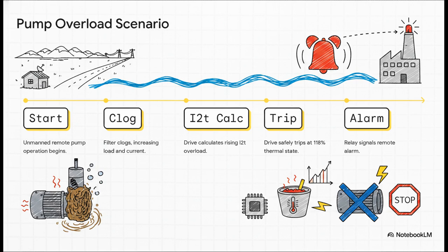But because a sharp electrician properly set the ITH thermal current parameter during commissioning, the drive's mathematical bucket began tracking that rising heat. Way before the motor windings had a chance to melt, the drive tripped at that 118% thermal state, shut down the power, and fired off a relay to signal a remote alarm back at the main plant.